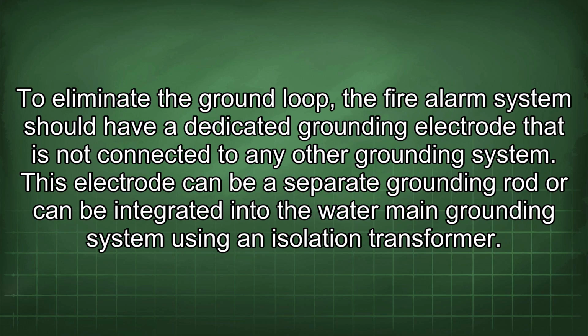To eliminate the ground loop, the fire alarm system should have a dedicated grounding electrode that is not connected to any other grounding system. This electrode can be a separate grounding rod or can be integrated into the water main grounding system using an isolation transformer.